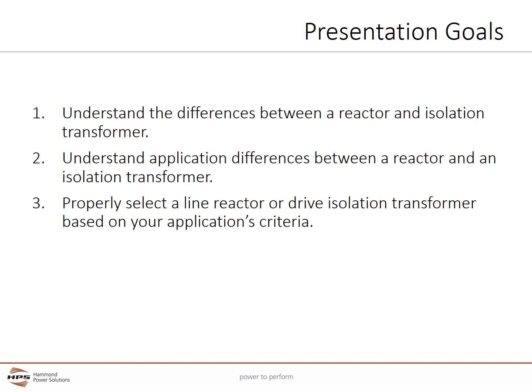There are three main goals for this presentation. Number one, understand the physical differences between a reactor and a drive isolation transformer when used with variable frequency drives or VFDs. Number two, understand the application differences between a reactor and an isolation transformer. And three, be able to properly select a line reactor or drive isolation transformer based on your application's criteria.